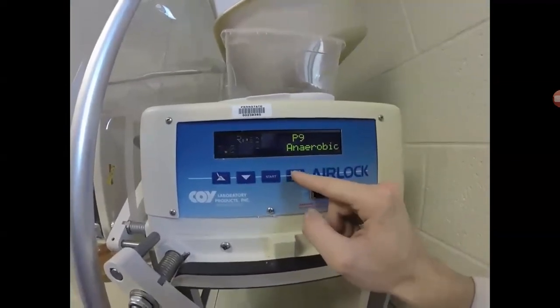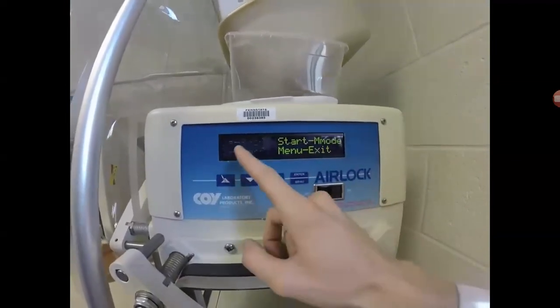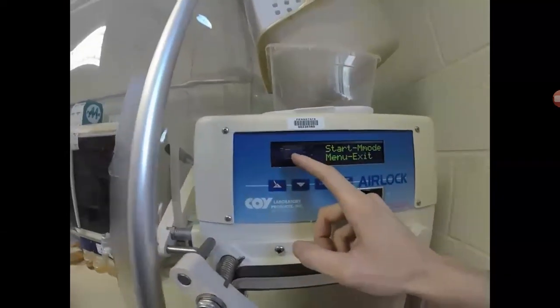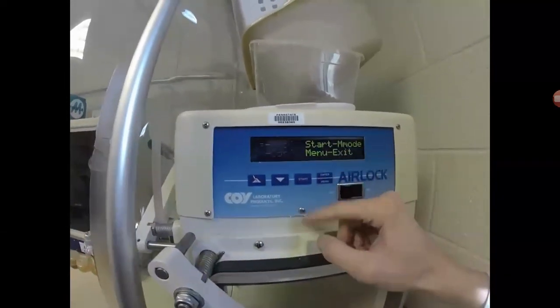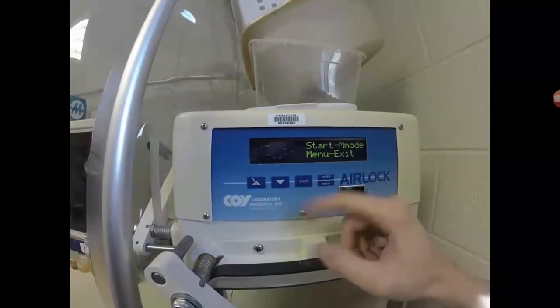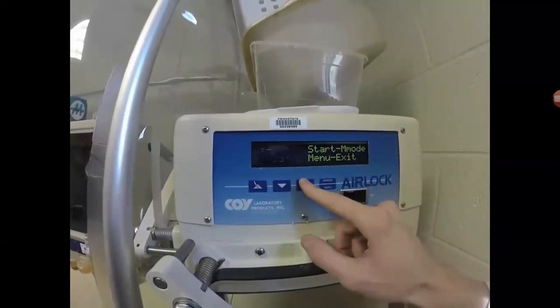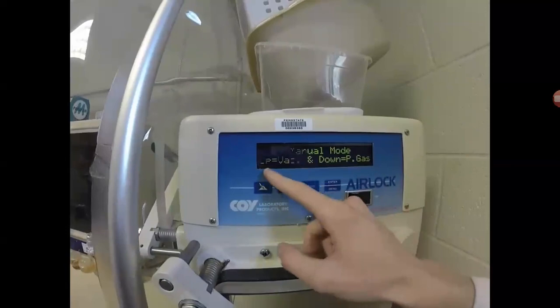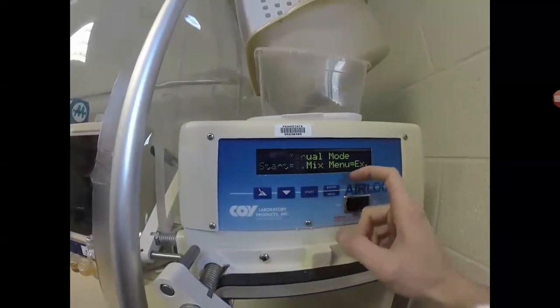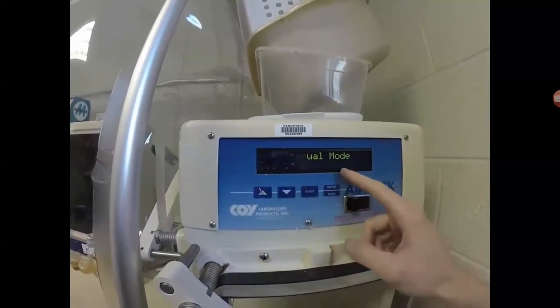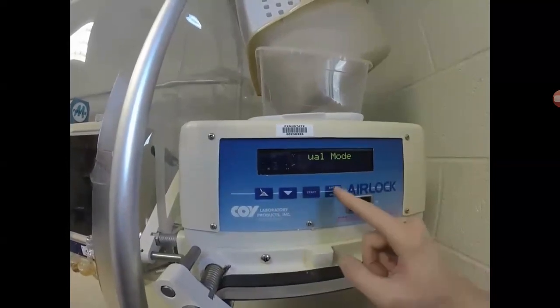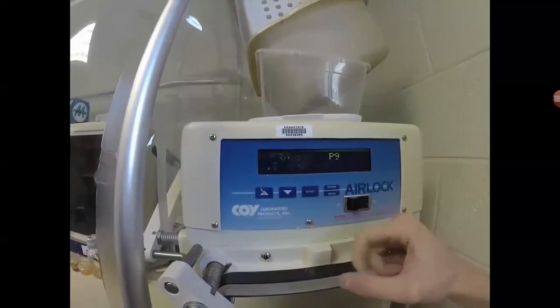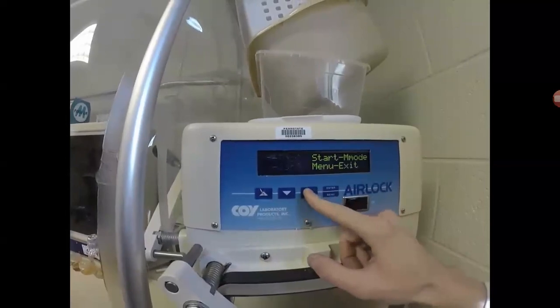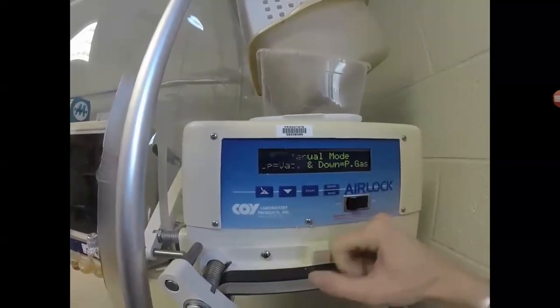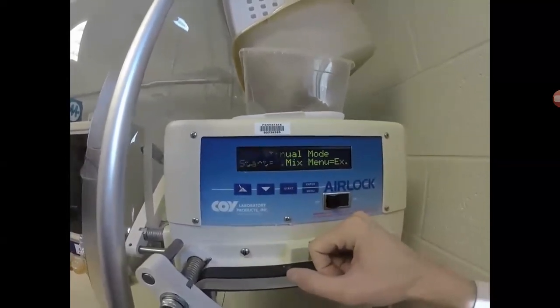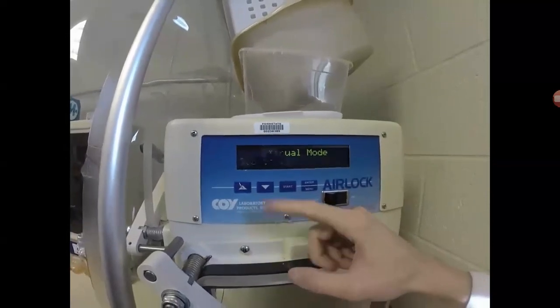In order to do that, we press menu. Now it gives you like 4 options here. You can't really see these ones, but that's okay because all you need is this one, which says start will take you to manual mode or M mode. So press start. Now it says manual mode, up equals vacuum, down equals purge gas, start equals mix, and menu equals exit. At this point, if we press menu, it gets us back to P9. I'll have to do that again. It's going to go through our little description again.